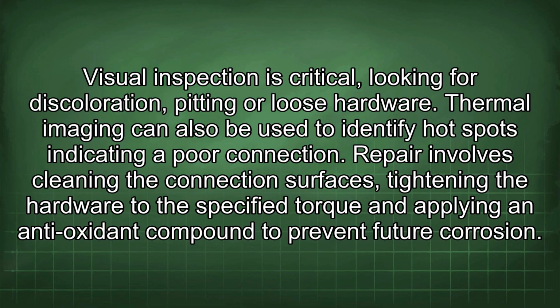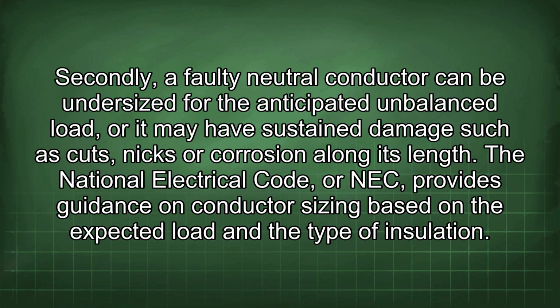Thermal imaging can also be used to identify hot spots, indicating a poor connection. Repair involves cleaning the connection surfaces, tightening the hardware to the specified torque, and applying an antioxidant compound to prevent future corrosion. Secondly, a faulty neutral conductor can be undersized for the anticipated imbalanced load, or it may have sustained damage such as cuts, nicks, or corrosion along its length.